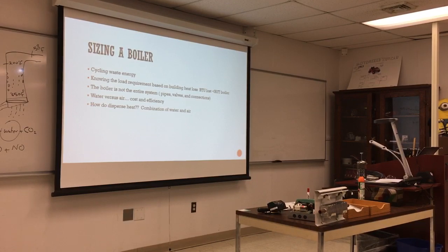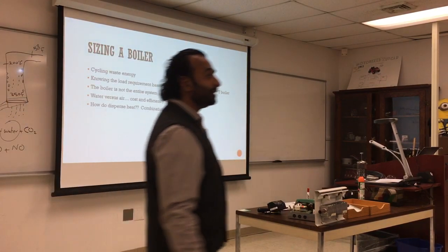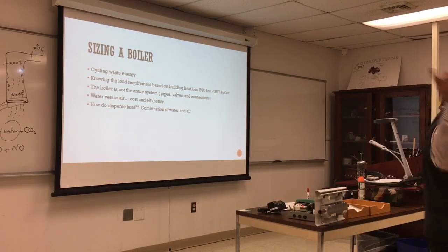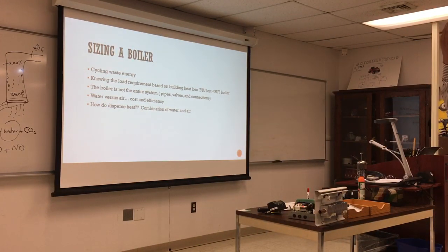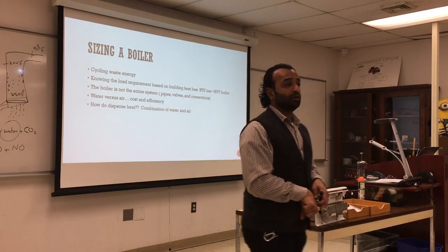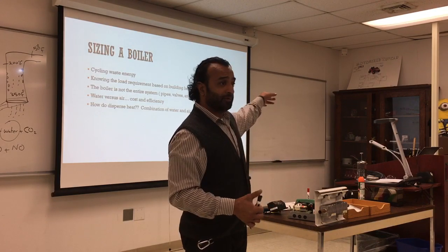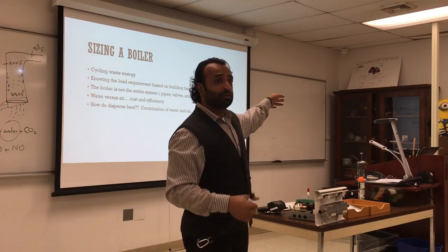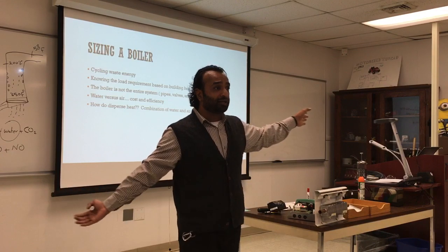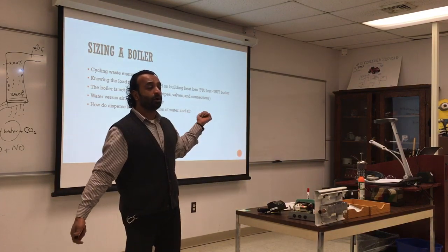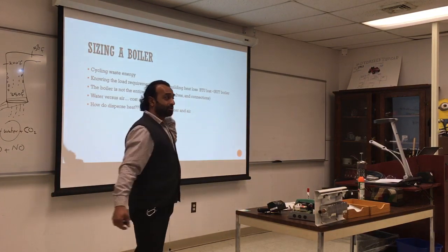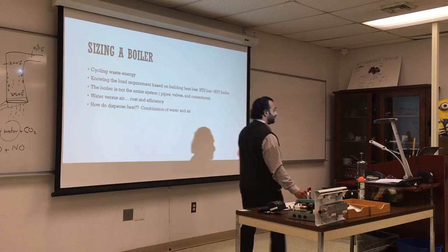So that condensate water just returns back to the boiler? Yeah, and gets steamed again. If you look outside here, we have a big fan with a radiator in it, and that's steam going through it. Through gravity, and through remote pumps. Condensate pumps. The pump is in the corner. So the condensate all goes into a tank, and the pump pumps the water all the way to building 17. So this is actually coming all the way to building 17.